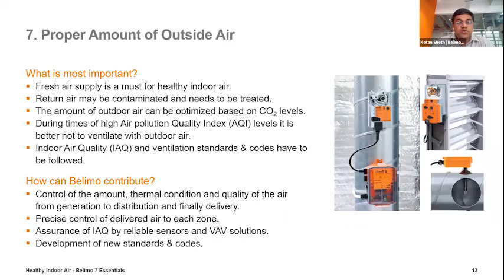The last is the proper amount of outside air. Like Mr. Mittal said, fresh air is not fresh air, it's outside air. So we have tried to capture that here. Return air may be contaminated, so we need to treat it. And specifically in terms of CO2 level, we have to add some outside air to dilute the CO2. But when the air quality index of the outside air is high, it is not recommended to ventilate with outside air. Indoor air quality and ventilation standard codes have to be strictly followed. It should not be compromised at the cost of energy efficiency.